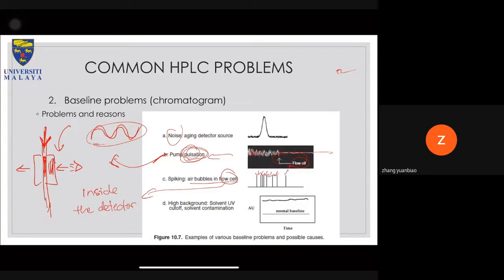Additionally, if you have a very high background, especially if you are using a UV-based detector, it might be due to the solvent wavelength cutoff or solvent contamination. Solvent cutoff is the graph that I showed you initially, whereby the cutoff is around 200 nanometers. If that happens, then your solvent is not really compatible, and it gives a quite high baseline reading. That might be okay in certain cases, especially if you know your analyte is at higher concentration. But if the analyte you are measuring is very minute, then having a high solvent UV cutoff is bad for your analysis.